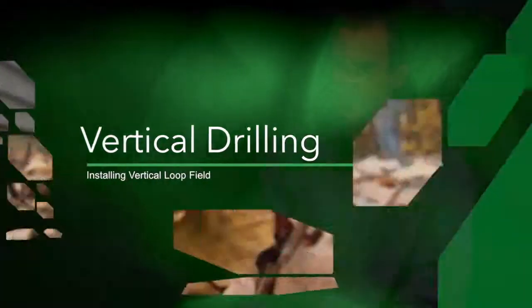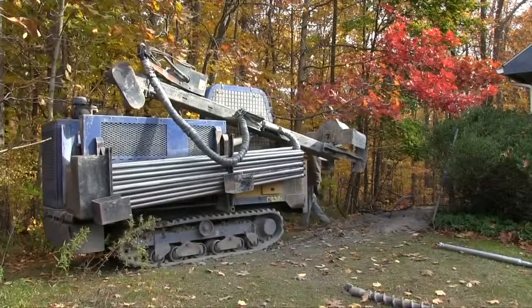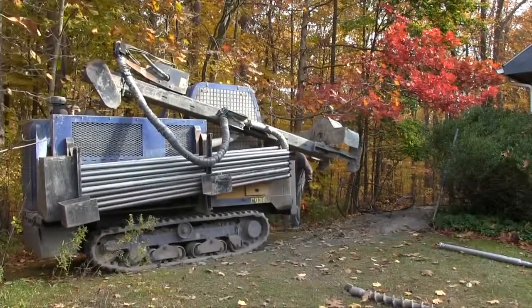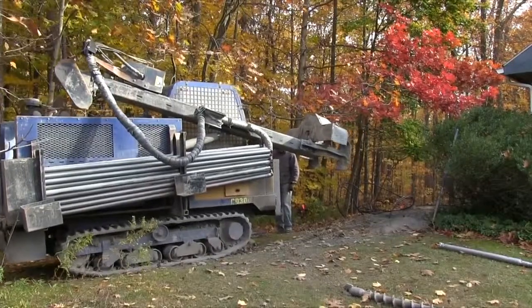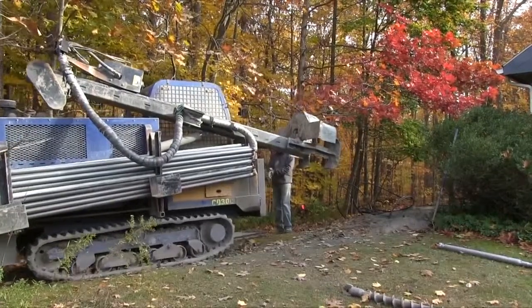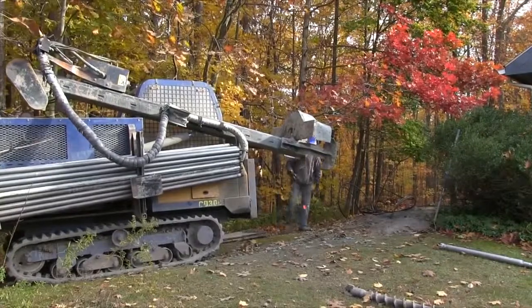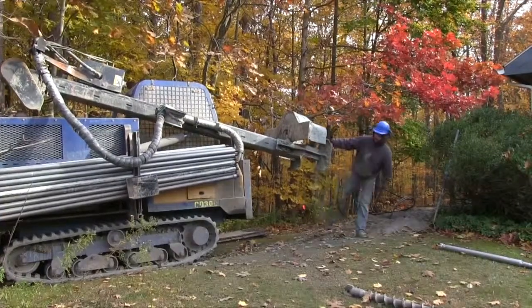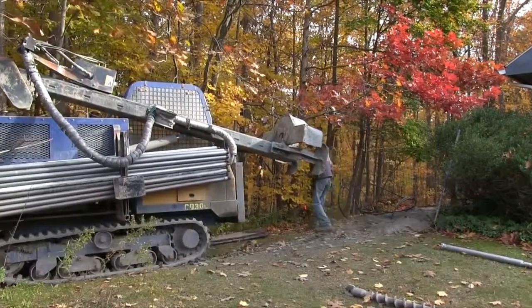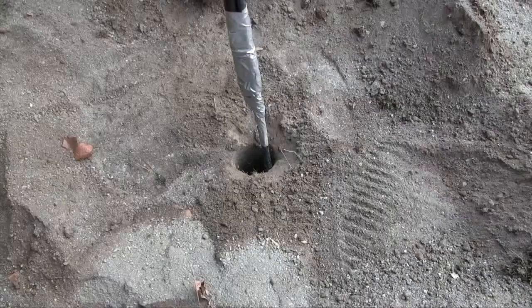When we perform a vertical drilled installation, we are showing up to a job site with a very small crawler-based drill that is completely self-contained. This drill is only 6 feet wide and 10 feet long. It comes in on rubber tracks. It makes about the same impression on the lawn as a garden tractor would. And with this drill, we're able to get down 200 feet deep with a 4-inch perforation. Once we've completed our bore, we're going to insert a geothermal loop inside the bore, and then we're going to fill that bore with a grout.